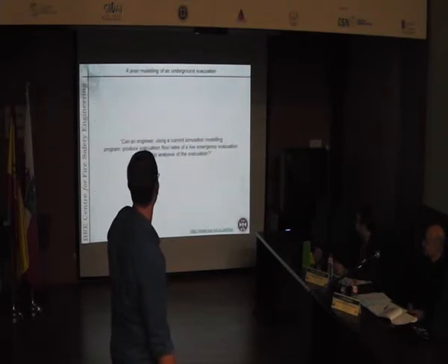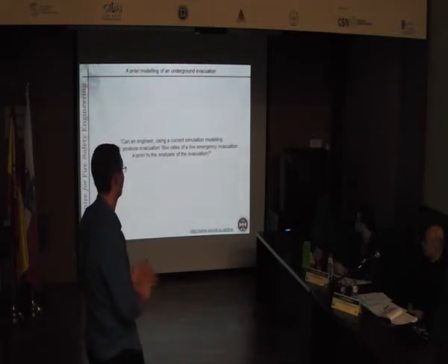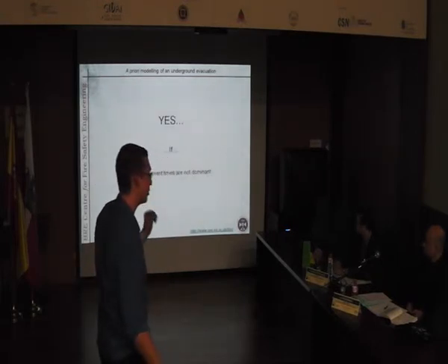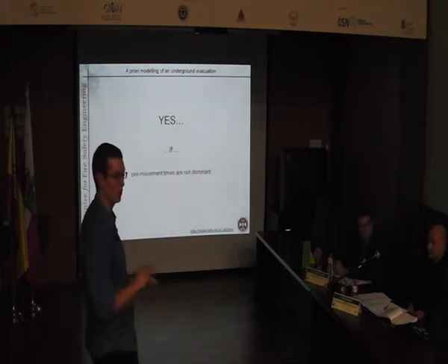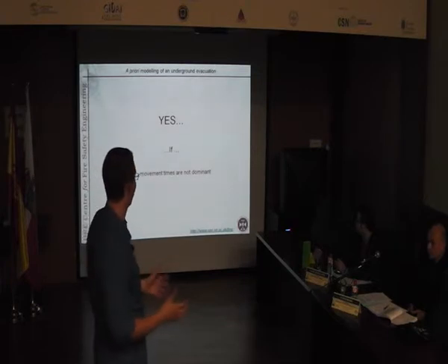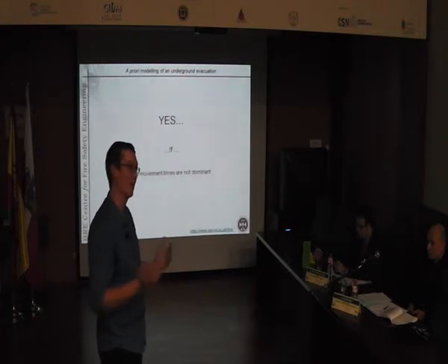So coming back to the question, can an engineer using a current simulation modelling program produce evacuation flow rates of a live emergency evacuation, a priori to analysis of the evacuation? In my case, yes. But if I had more dominant pre-movement times, then no. Pre-movement time, because of the whistle, it took it away, and I couldn't predict the pre-movement time. I tried predicting the pre-movement time with an actual live evacuation, and the model did not work at all. So it comes down to the fact that if you remove behaviour, then this model works, but unfortunately you can't remove behaviour from an actual live evacuation, only experimental evacuations.